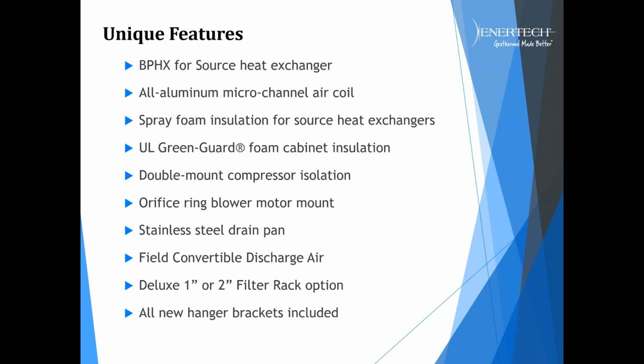We have a double mount compressor isolation system. Our double mount compressor isolation system is highly engineered. We use these specific pads that are called Getzner pads. They're made out of elastomeric high-density material, and it's designed based on the weight of the compressor. So highly engineered to absolutely take out all noise, all sound, all vibration to make a really excellent, quiet machine that you just won't be able to hear it.